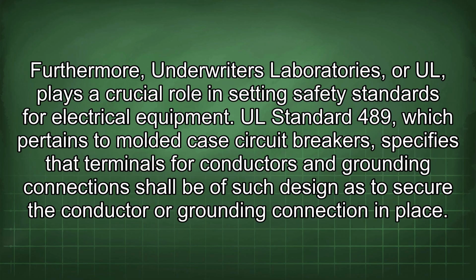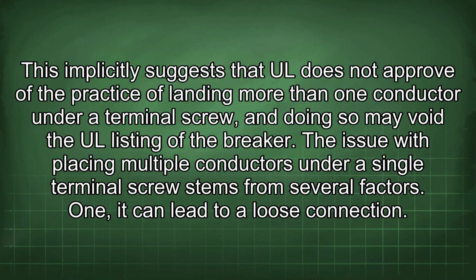Furthermore, Underwriters Laboratories, or UL, plays a crucial role in setting safety standards for electrical equipment. UL Standard 489, which pertains to molded case circuit breakers, specifies that terminals for conductors and grounding connection shall be of such design as to secure the conductor or grounding connection in place. This implicitly suggests that UL does not approve of the practice of landing more than one conductor under a terminal screw, and doing so may void the UL listing of the breaker.